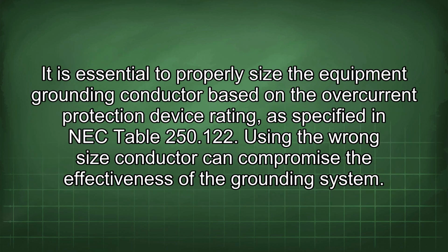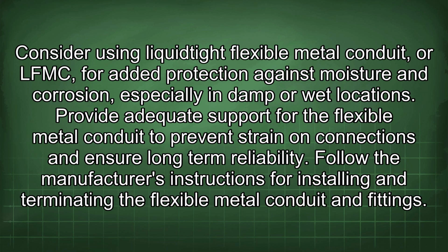It is essential to properly size the equipment grounding conductor based on the overcurrent protection device rating as specified in NEC Table 250.122. Using the wrong size conductor can compromise the effectiveness of the grounding system. Consider using liquid-tight flexible metal conduit, or LFMC, for added protection against moisture and corrosion, especially in damp or wet locations. Provide adequate support for the flexible metal conduit to prevent strain on connections and ensure long-term reliability.